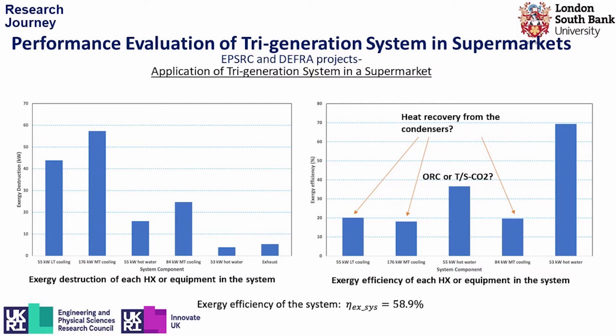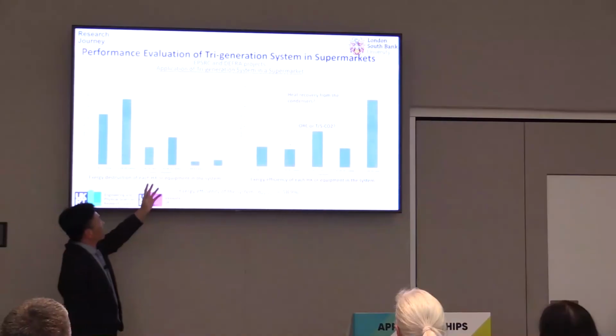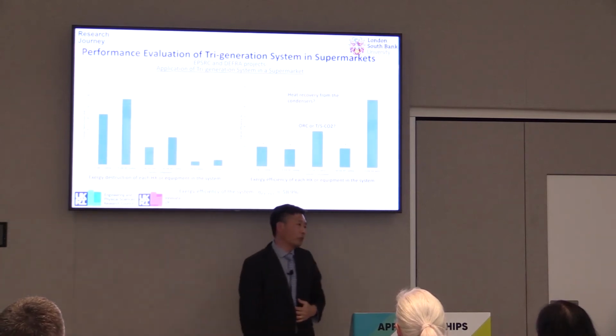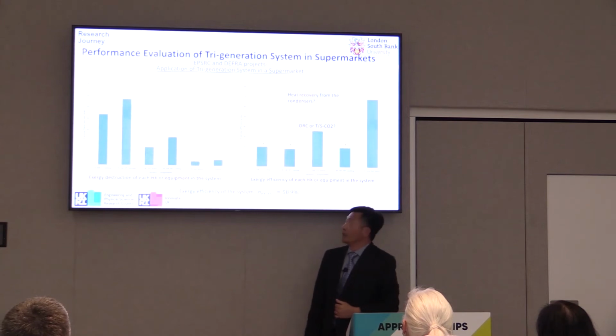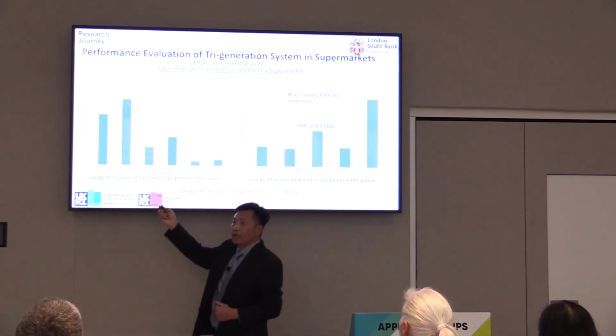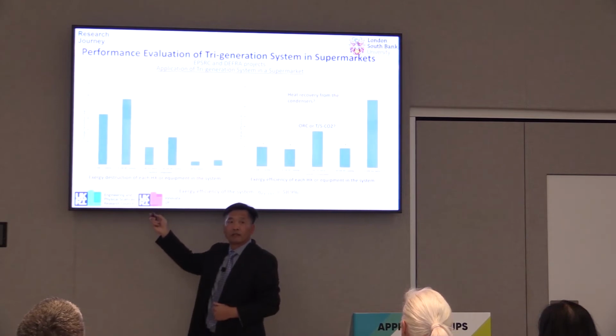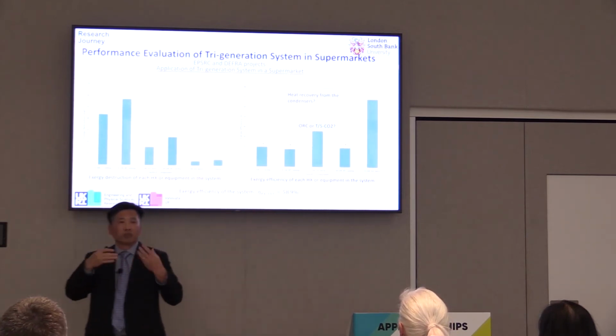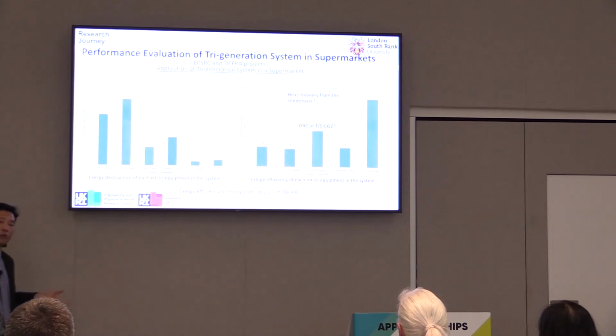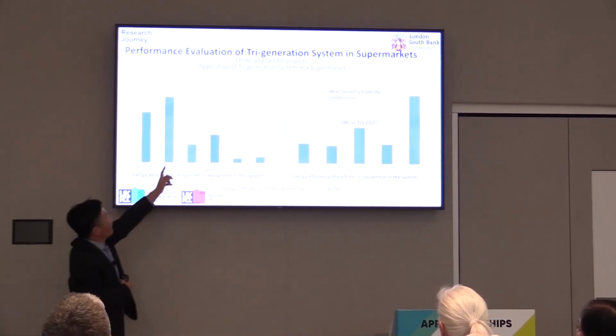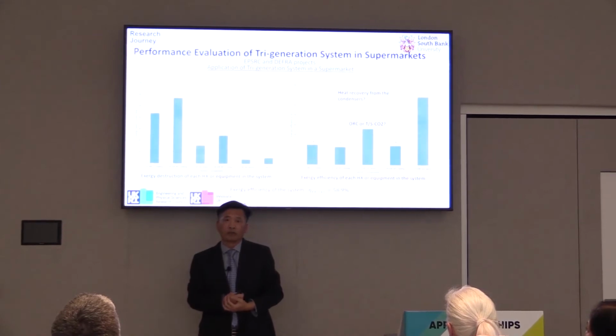By using this exergy analysis, to summarize here, for each equipment or heat exchanger, we carried out the exergy destruction for each one. So for this LT cooling and MT cooling and the hot water and also the MT cooling from the absorption, this is the exergy destruction. Correspondingly, we calculate the exergy efficiency for each equipment and heat exchanger. So we need to look at the largest exergy destruction, where the useful work has been destroyed. We need to find a way to produce more useful work. This is what we call the weak link we need to think about for the design.